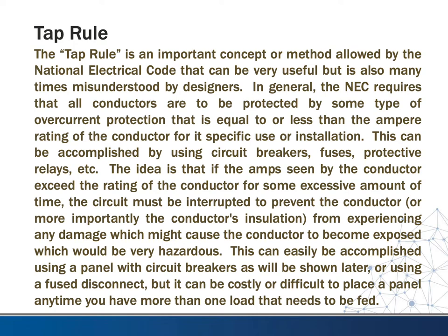But the idea is that if the amps seen by the conductor exceed the rating of the conductor for some excessive amount of time, the circuit must be interrupted to prevent the conductor, or more importantly, the conductor's insulation, from experiencing any damage which might cause the conductor to become exposed, which would be very hazardous. This can easily be accomplished by using a panel with circuit breakers, as will be shown later, or using a fuse disconnect, but it can be costly or difficult to place a panel anytime you have more than one load that needs to be fed.